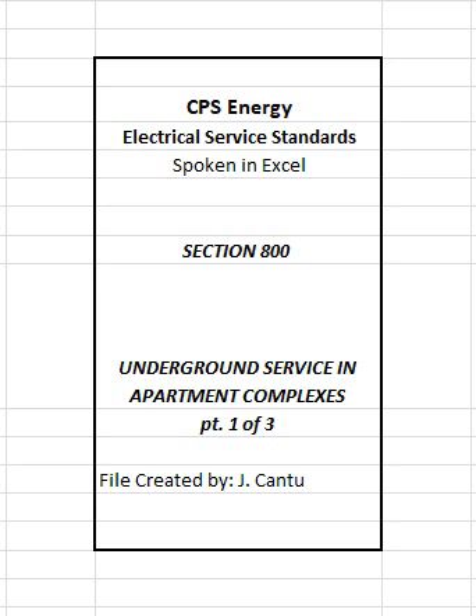A. Restricted use of easements. Customer shall not permit any structure, such as storage buildings, swimming pools, spas, decks, patios, carports, garages, concrete walks, and drives or equipment to be temporarily or permanently positioned within easements. B. Call before digging. Texas law requires anyone who plans to excavate to notify 1-800-DIG-TESS or 811 for location of underground facilities at least 2 working days in advance so that the utility lines can be located and marked for safety. Refer to helpful numbers listed on the inside front cover page.